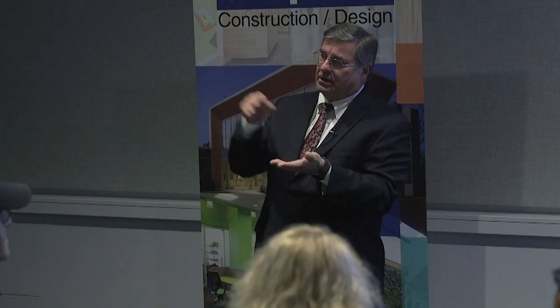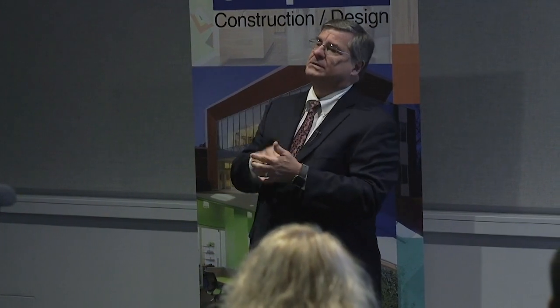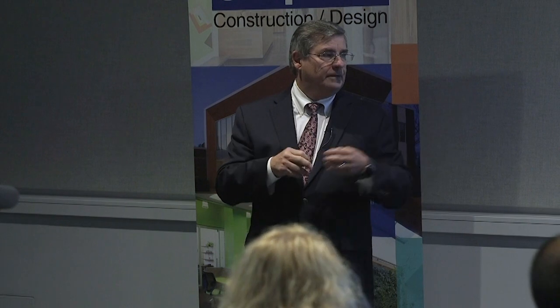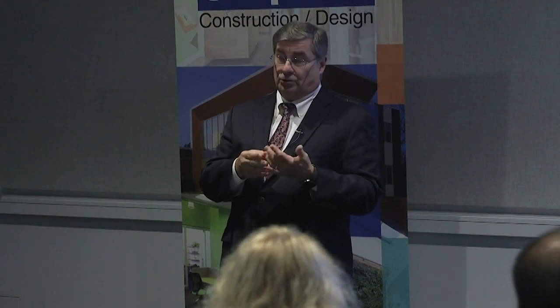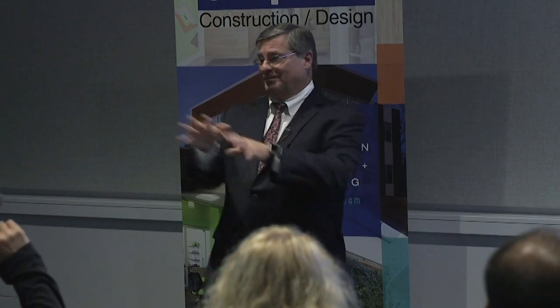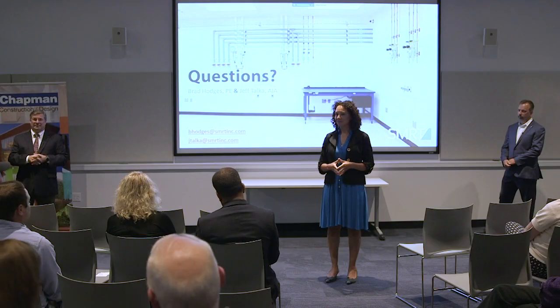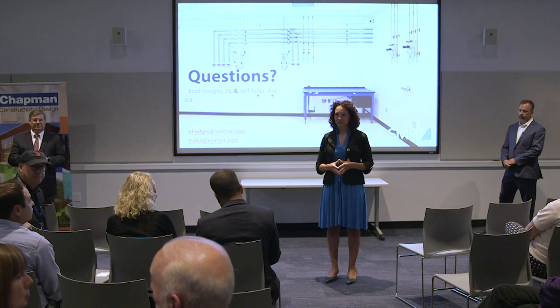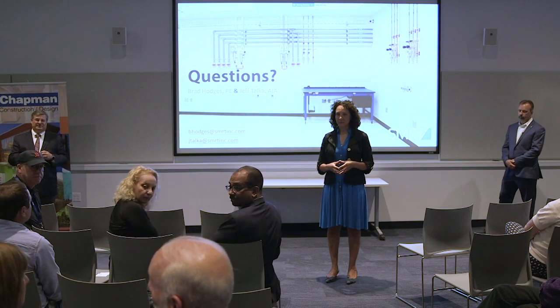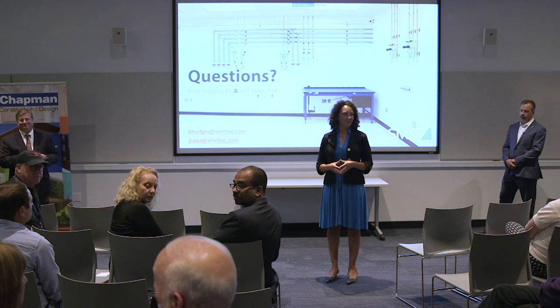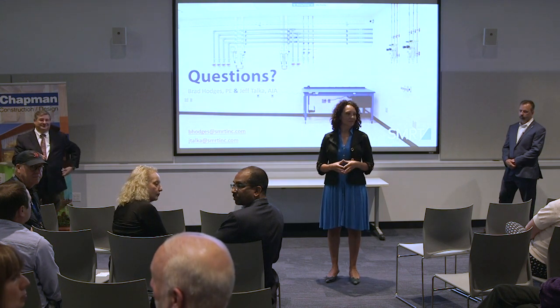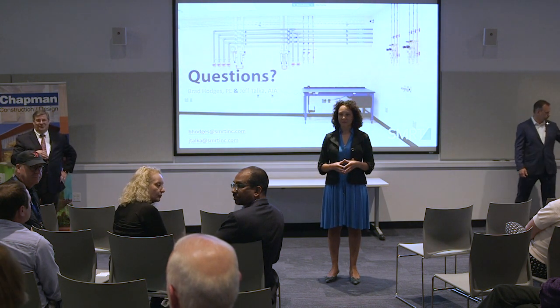But as you progress higher and higher, biological laboratories, chemistry laboratories, the more intensified laboratories, up through biosafety levels, that can be $1,500 a square foot. So it's going to depend on fume hood intensity, air exchange rates, your risks, the materials. I'm sorry to be so glib about it, but it's kind of an open-ended question. Getting back to the point Brad made about energy, microelectronics is going to be well over 2,000 a square foot because of everything that's going into it and being consumed. Well, I forgot it's in Boston.